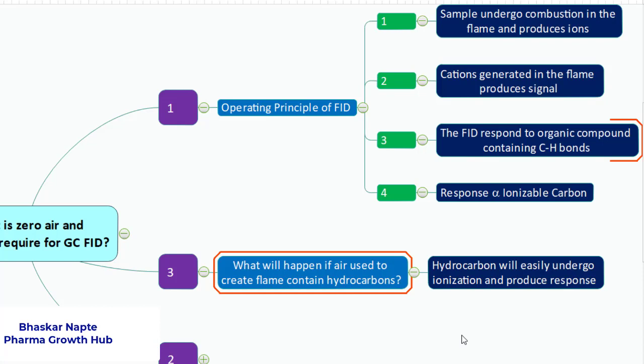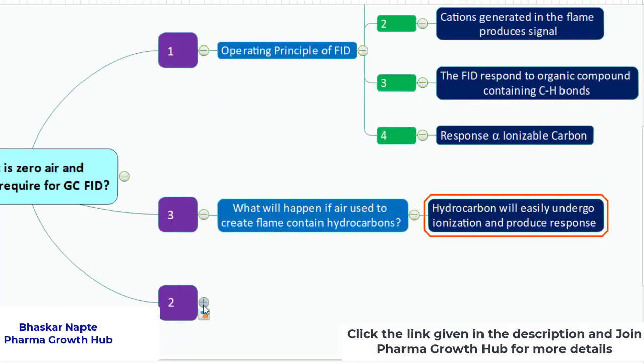So you must have understood that you must use air which should not contain hydrocarbons. Now what is the link between hydrocarbons and zero air? Zero air stands for what? There is a zero and then there is air. So air containing something zero, and what is that zero quantity? It is the hydrocarbons quantity. Means if your air does not contain hydrocarbons, that air is called zero air.